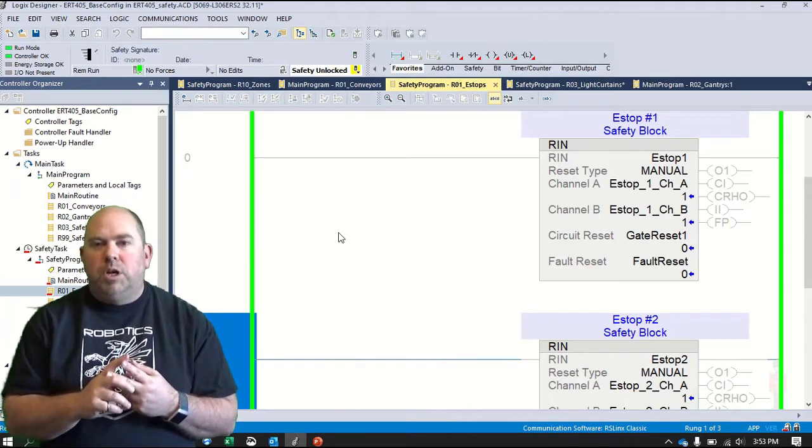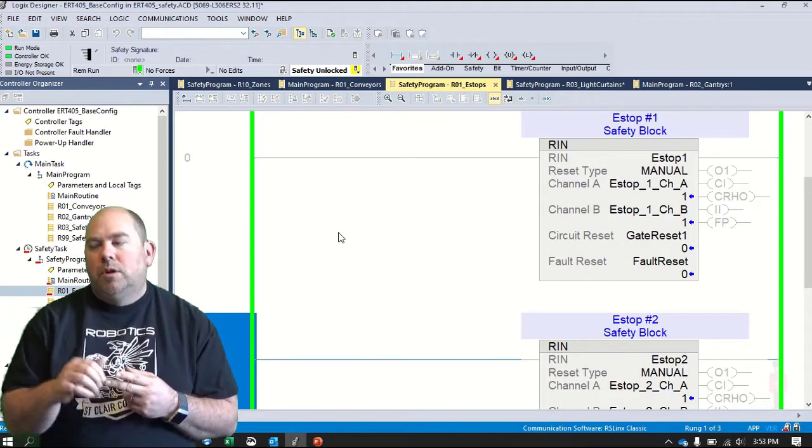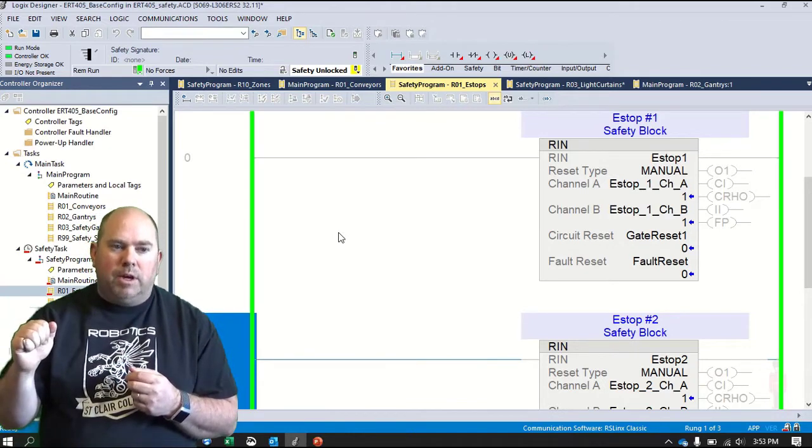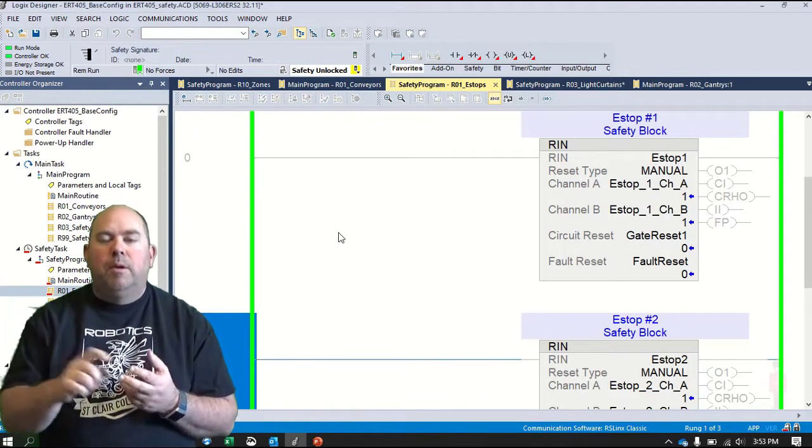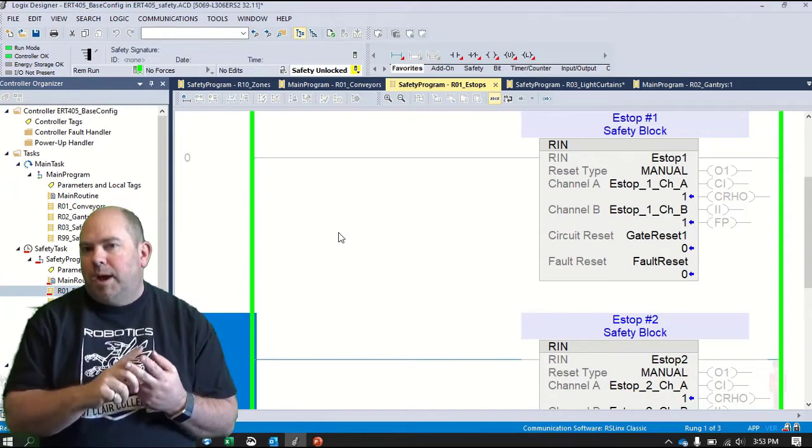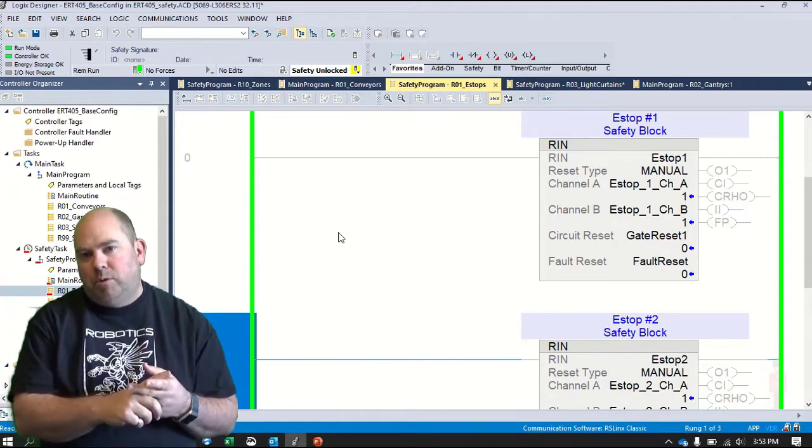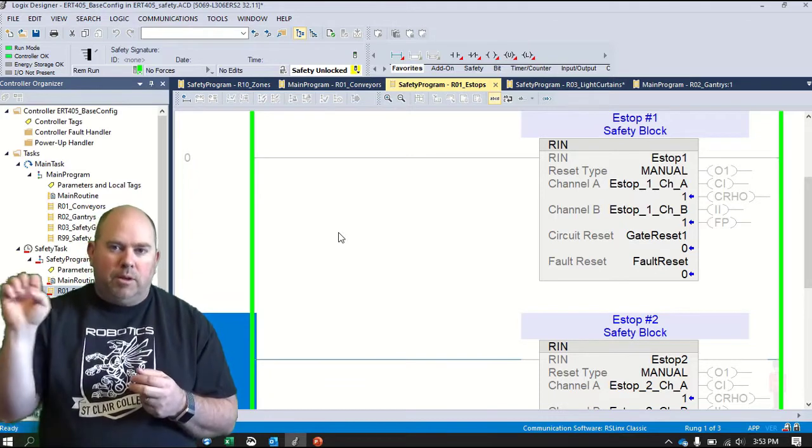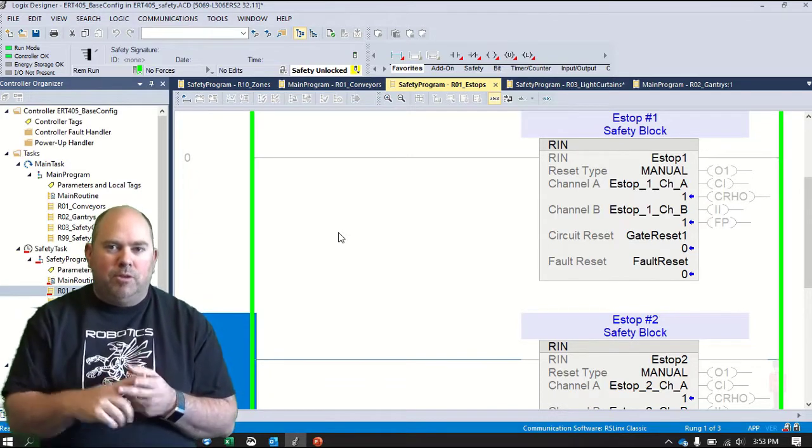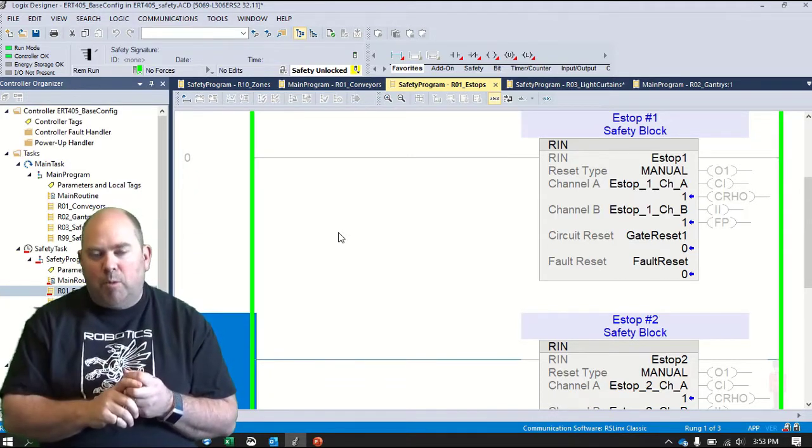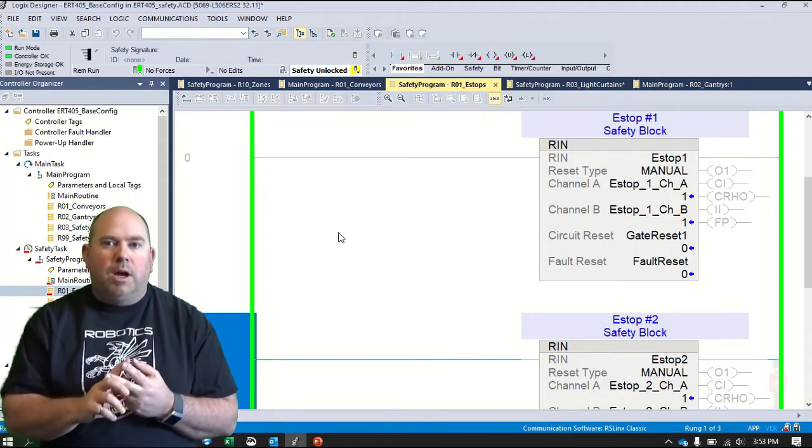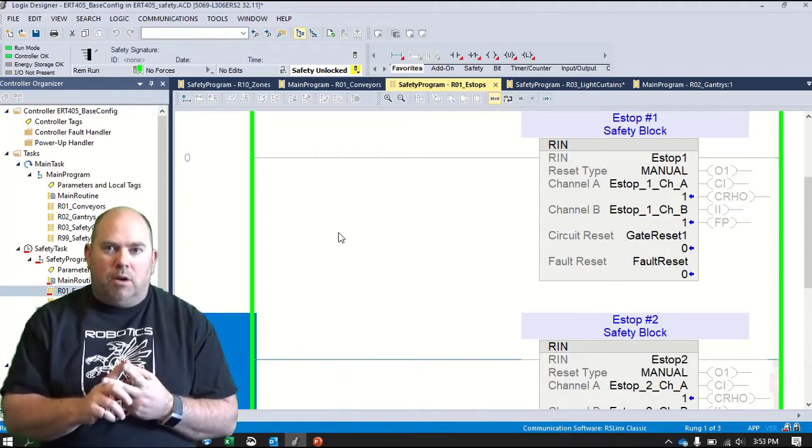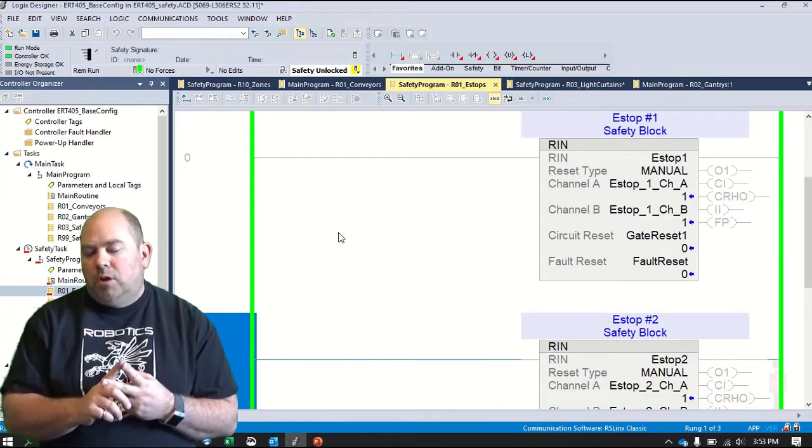So you'll need to go to every single safety device, basically toggle that device. So if it's an e-stop, press the e-stop. You want to see, does that e-stop actually shut down what it's supposed to shut down? Pull that e-stop back out again. It shouldn't restart until you restart it the proper way. And then the other thing we're going to want to do is, does the block actually function to detect all the fault conditions that it should?